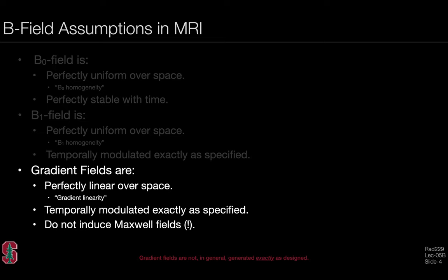This slide was used previously to discuss some of the B-field assumptions in MRI, focusing on those associated with gradient fields. We assume they are perfectly linear over space, which was covered in a previous lecture. We also assume that gradient fields are temporally modulated exactly as specified, and we do not typically include Maxwell fields. This lecture focuses on whether we temporally modulate gradient fields exactly as specified, specifically as a consequence of eddy currents.